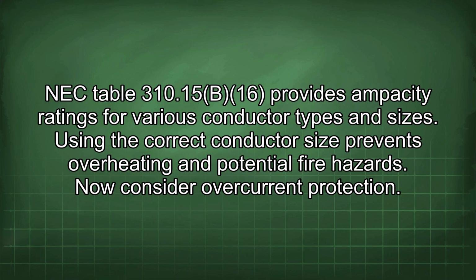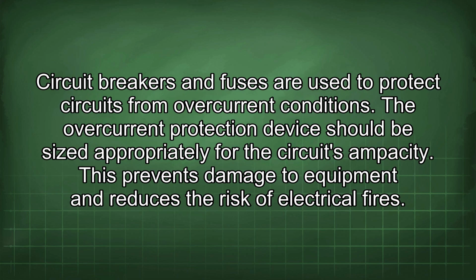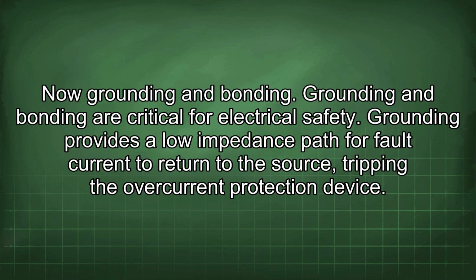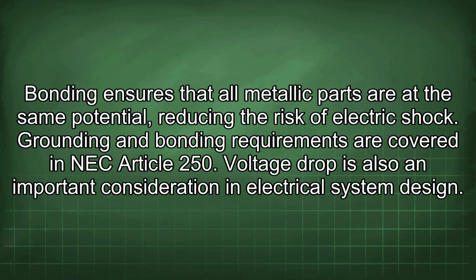Now consider overcurrent protection. Circuit breakers and fuses are used to protect circuits from overcurrent conditions. The overcurrent protection device should be sized appropriately for the circuit's ampacity. This prevents damage to equipment and reduces the risk of electrical fires. Now grounding and bonding. Grounding and bonding are critical for electrical safety. Grounding provides a low impedance path for fault current to return to the source, tripping the overcurrent protection device. Bonding ensures that all metallic parts are at the same potential, reducing the risk of electric shock. Grounding and bonding requirements are covered in NEC Article 250.